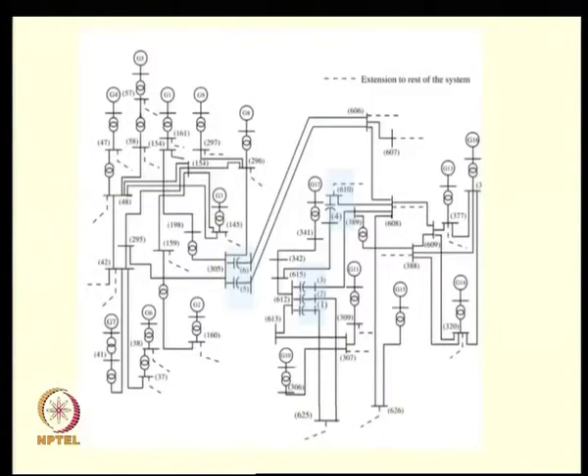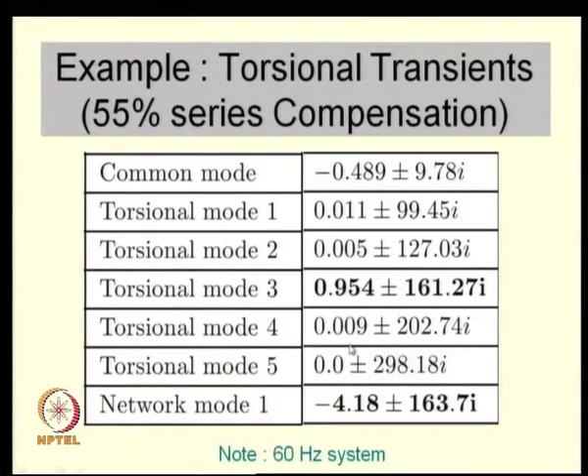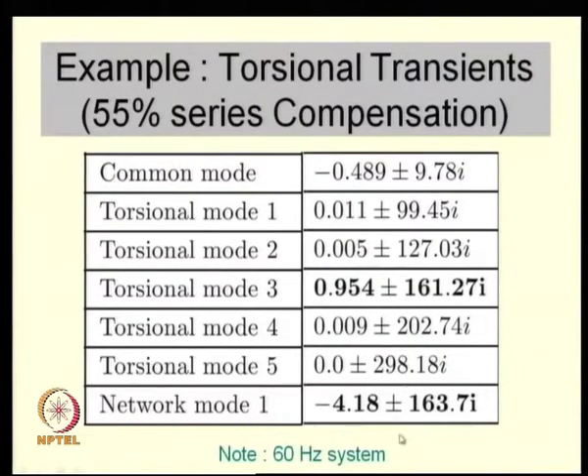How can you avoid sub-synchronous resonance? One way is to prevent coincidence of the network mode with a torsional mode. If there is no coincidence, the effect on other torsional modes is quite low. Torsional modes 1, 2, and 4 have low adverse interaction, and with mechanical viscous damping present they would be stable. The problem comes in torsional mode 3 where there is a good coincidence, so it makes sense to limit series compensation to avoid that coincidence.